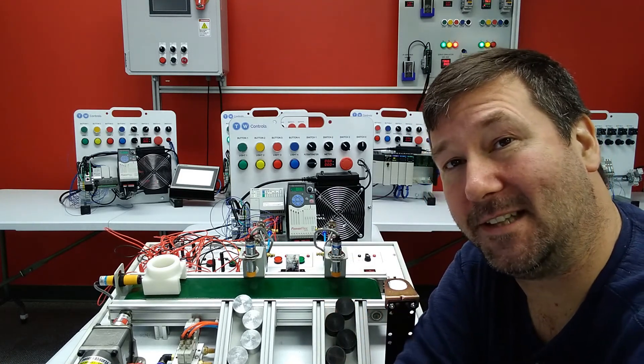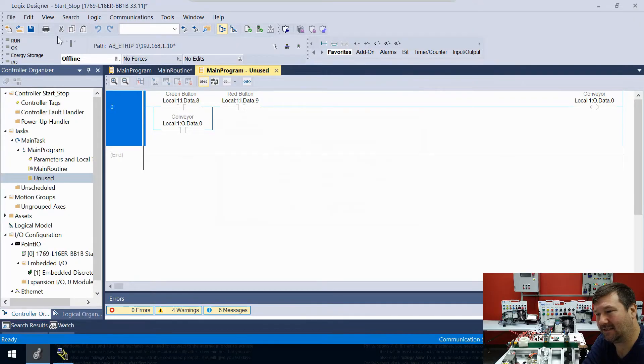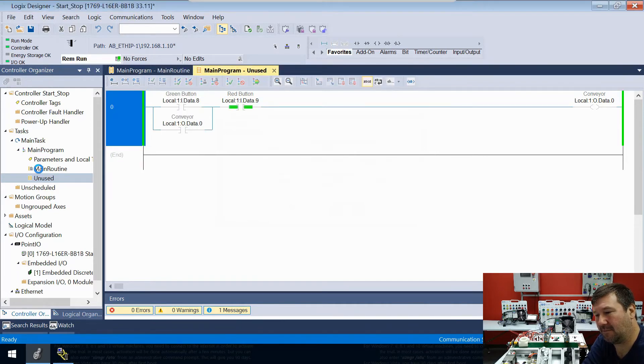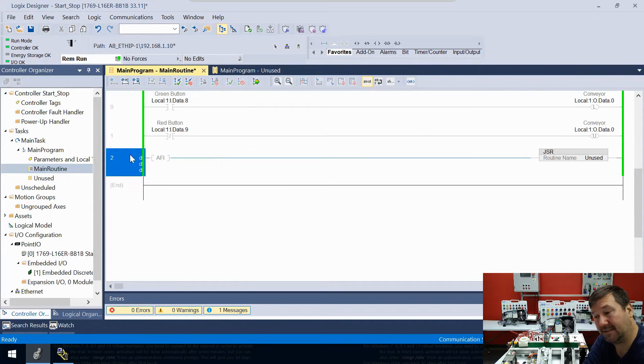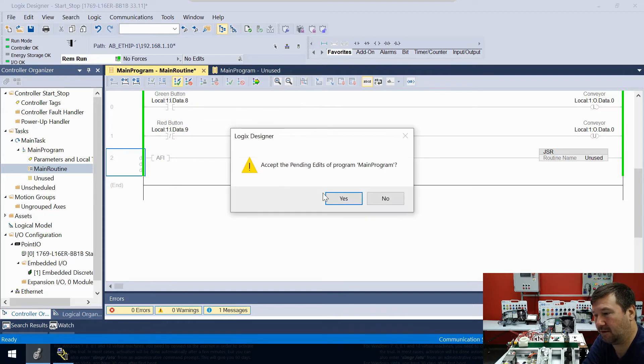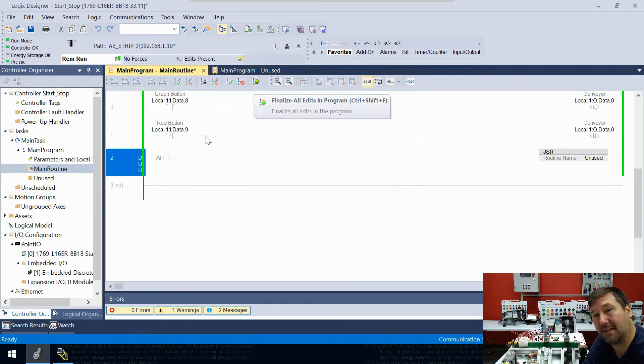I just had a thought and honestly I don't know how this will work — let's go back online, go to our main routine, highlight rung 2 and hit the delete key. This didn't just delete the rung right now — we got lowercase d's which means it's deleted in our program but not yet finalized. We're going to accept that pending rung edit.